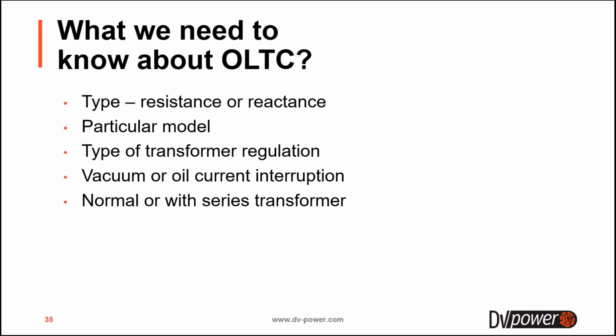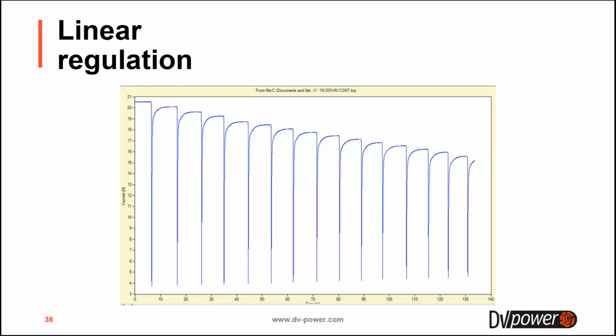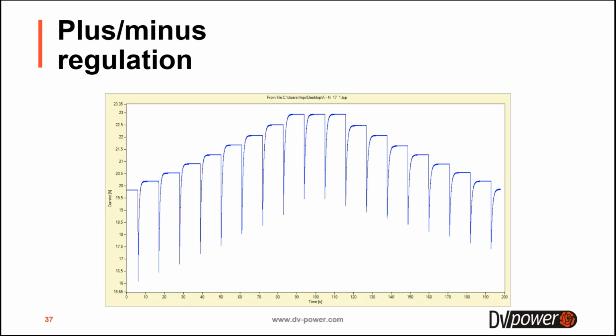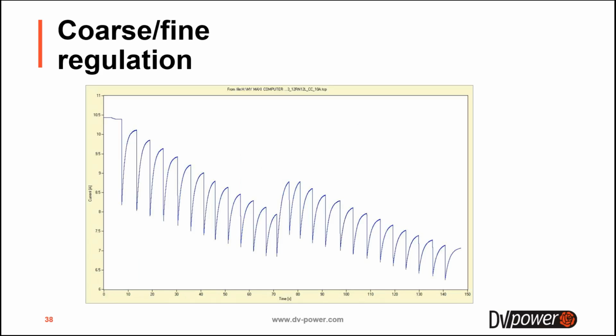So this is a typical graph of an OLTC that has a linear regulation. What is characteristic here is that the current keeps dropping. It has a linear drop because of the linear transformer regulation. It can decrease or it can increase depending on what direction you are recording, from first to the last position or from the last to the first. If it's plus-minus regulation, the overall graph can be a V or inverted V shape. And if it's coarse-fine regulation, then you have something like this. Up to the nominal position, you have a decrease of current, then in nominal position, you have an increase, and then again after the nominal position, you have a decrease of the current.